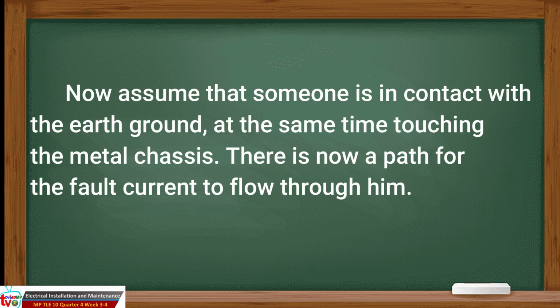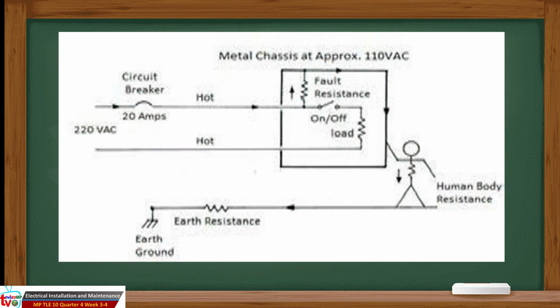Suppose someone is in contact with the earth ground at the same time touching the metal chassis. There is now a path for the fault current to flow through him. This is depicted in Figure 3. For the circuit to trip, the sum of the three resistances in the fault path must be less than 5.5 ohms. The internal resistance of the human body from one limb to any limb is approximately 500 ohms.